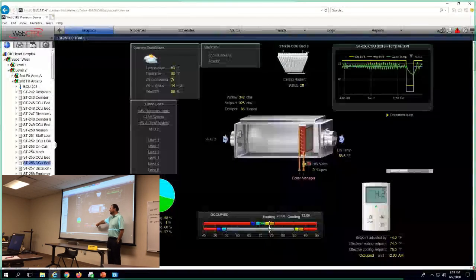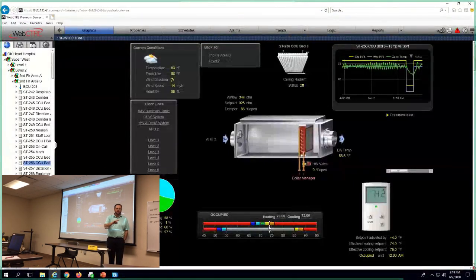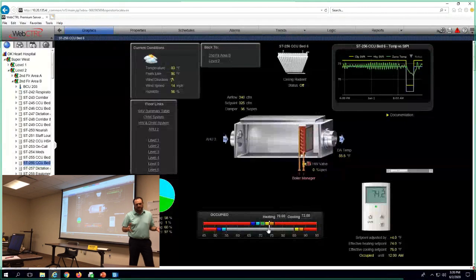So this set point, in the whole facility on all your equipment, is the parameters you guys want them to maintain. And then you give them the opportunity to adjust it up or down a certain amount. The reason for this is, one, we're concerned, probably more in hospitals and almost anywhere, with occupant satisfaction and comfort, because people are hot, cold, people are sick, don't feel good, but we want them to maintain some kind of parameters.